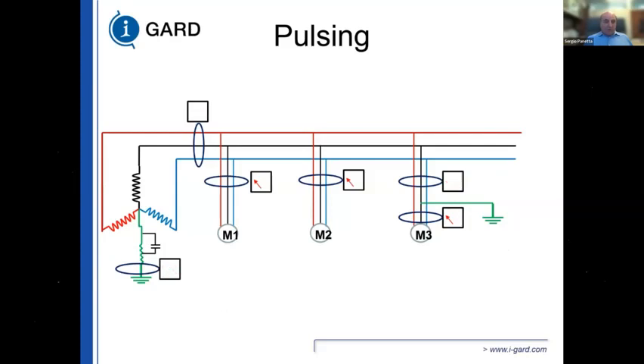So when you turn the pulsing on, only the faulted path will indicate this cyclical pulsing signature. So you can find exactly where the path of the fault is and exactly where the point of the fault is. As soon as you pass the point of the fault right there, you're back to normal system currents. So you can find where the fault is in any size facility in less than an hour. And more importantly, you don't even have to open up any doors to do this because you can actually detect this signature around conduit.